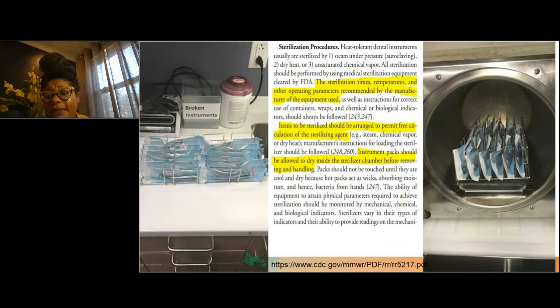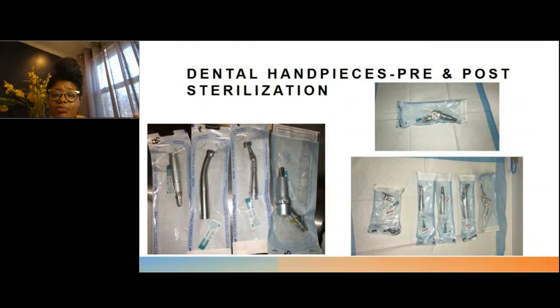Sterilizers have maximum weights, and you do also need to understand that it's a process, and you have to develop it based on the equipment that you have. Dental handpieces, pre and post sterilization. The feel and the look of a peel pouch before it goes into a sterilizer is totally different than when it comes out. So it's also important that the chemical indicators are on the inside, because they are your visual cues that they have been exposed to time, temperature, and steam penetration.